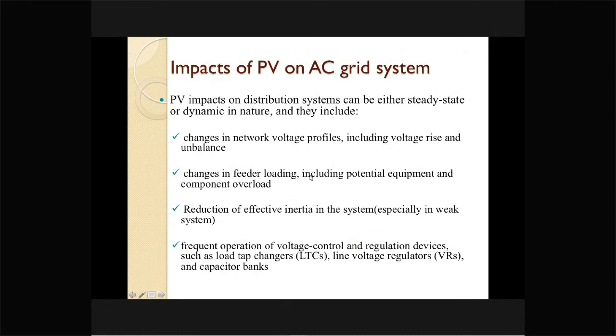Similarly, the feeder loading, including potential equipment and component overload, can be another impact of the photovoltaic integration. Besides, you can have the inertia of the system reduced by a large magnitude, and this becomes specifically significant for a weak system. Not the least, you can see the operation of OLTC, that is on-load tap changer, and line voltage regulator, as well as switched capacitor bank operation, becomes more frequent when the photovoltaic system is integrated. So this is the challenge when we go for the integration of PV into the AC grid: how to handle these issues.